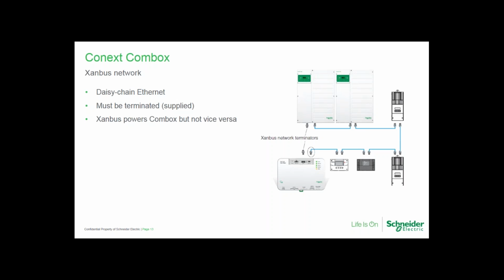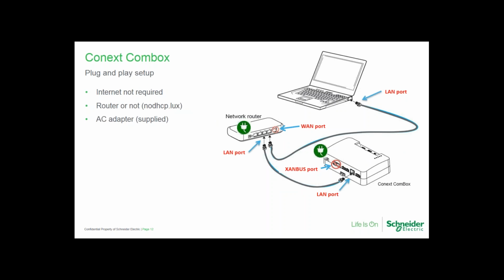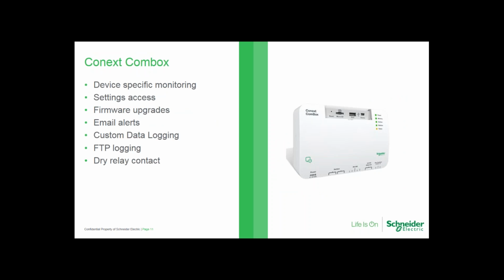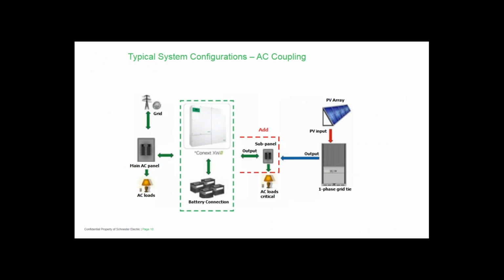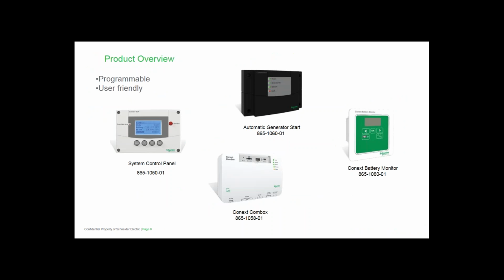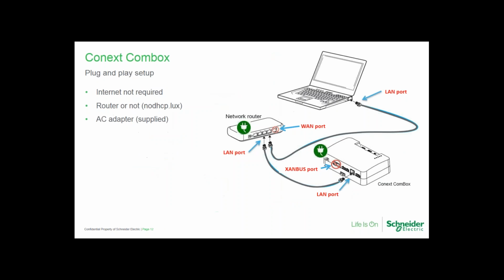Eric, our next question is, does the router have to stay powered up during a firmware upgrade? Should they put the system in bypass mode? Yes, absolutely, and yes again. That has been a sticking point for many off-grid installers, where you start the upgrade process and the inverter loses power, and the inverter just happened to have been powering the router. So then the upgrade process is interrupted. Then the device doesn't know what model it is. It'll know it's an inverter, but it won't know what model, or if it's a charge controller, likewise.